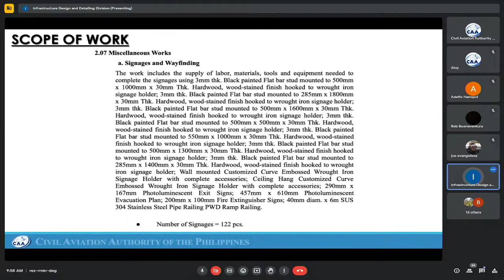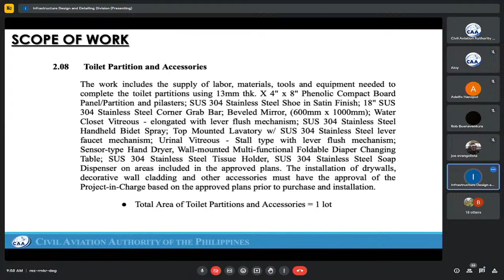And for signages, a total of 122 pieces of signages. And then for toilet partition and accessories, this will be one lot. And then for electrical works, lighting and power conduits and fittings, and then lighting and power conductors. Conductors shall be color coded as follows: for ground, green; line 1, red; line 2, yellow; and line 3, blue.